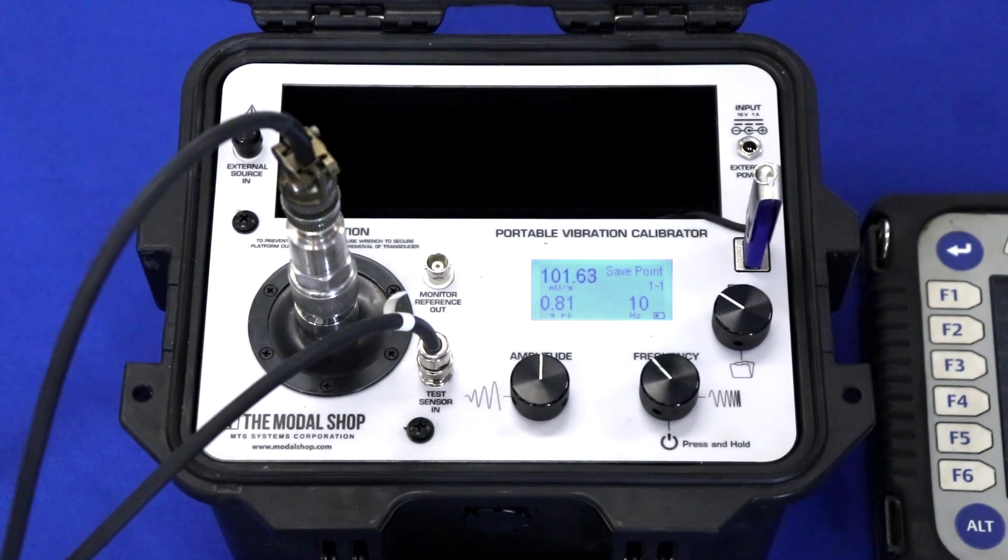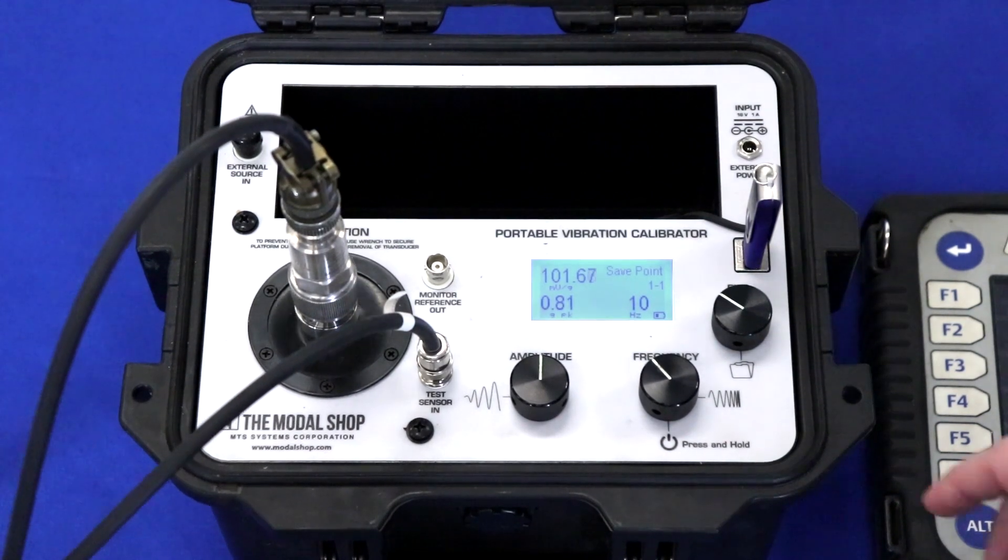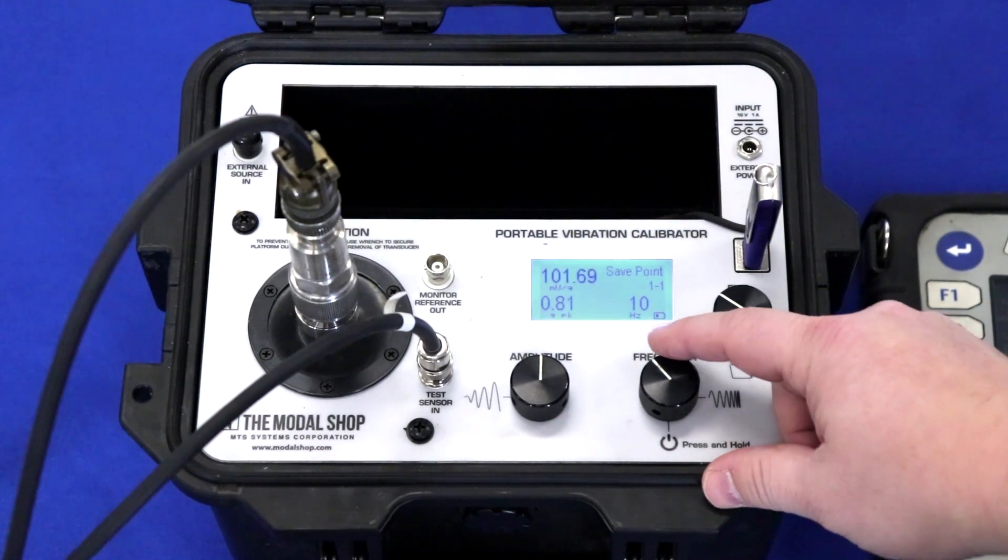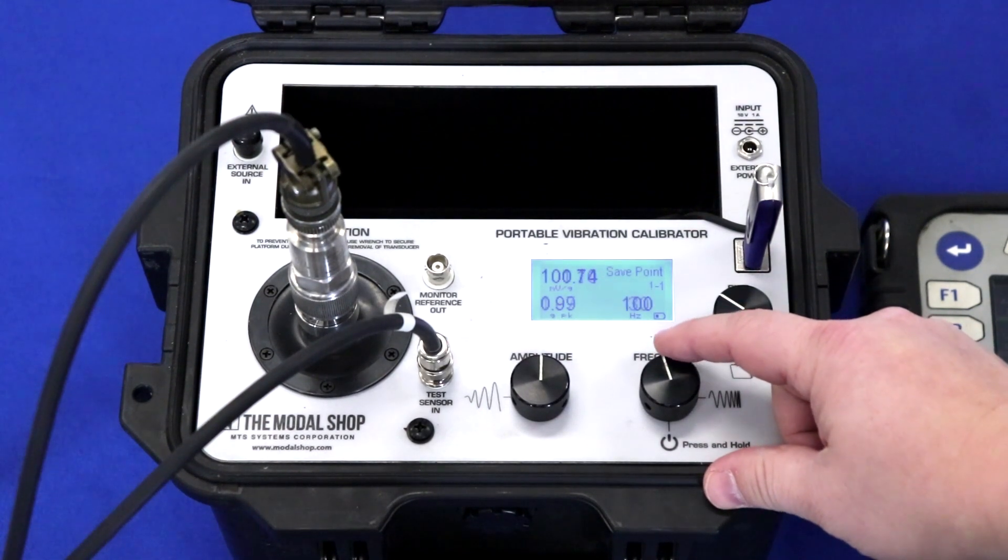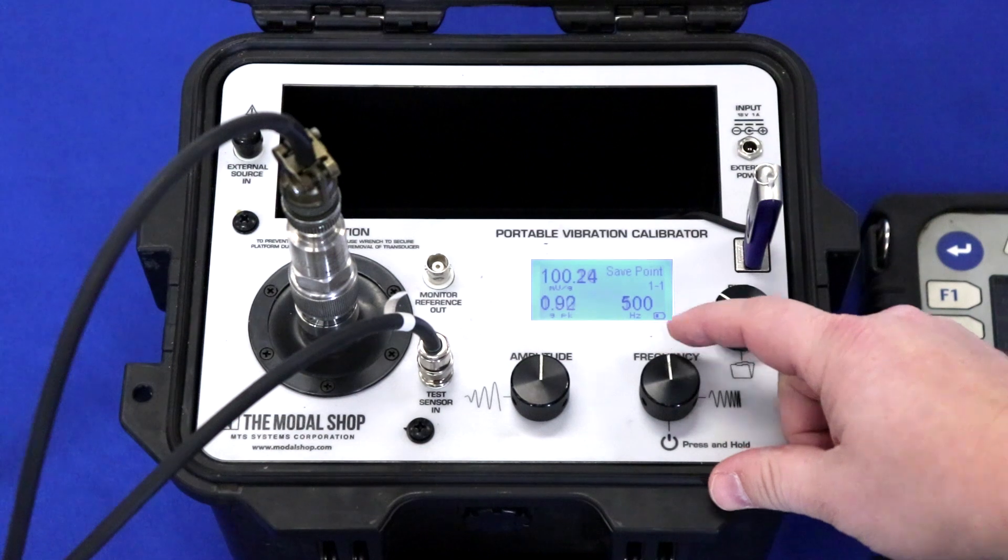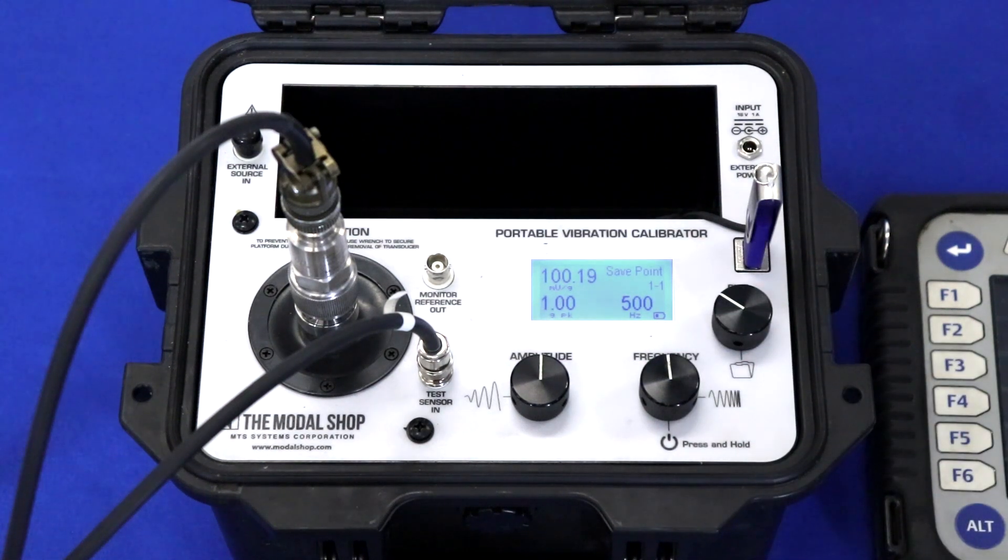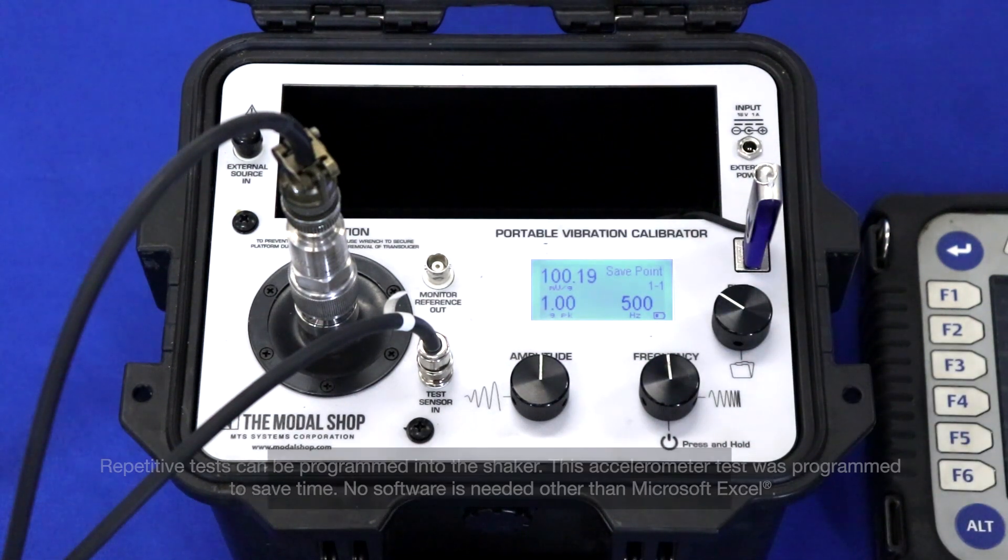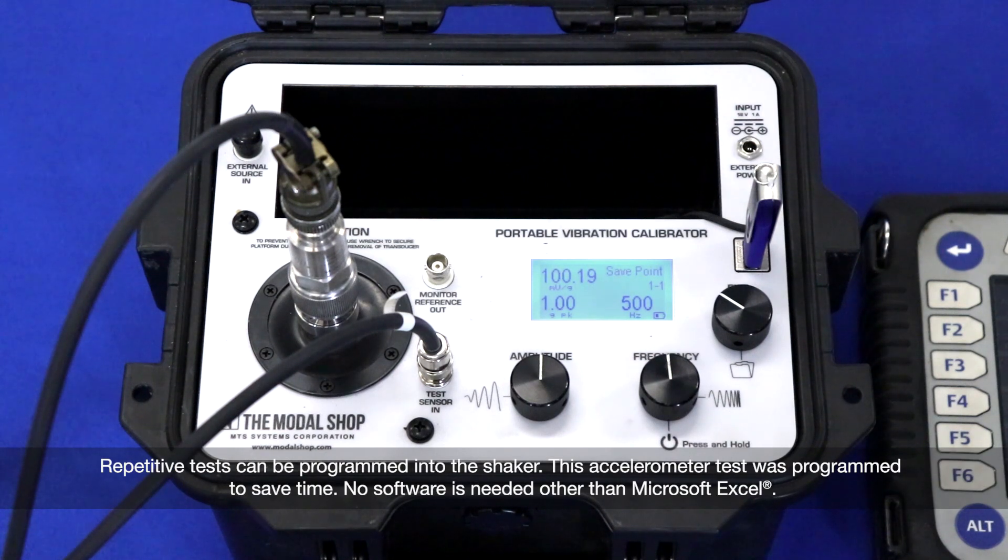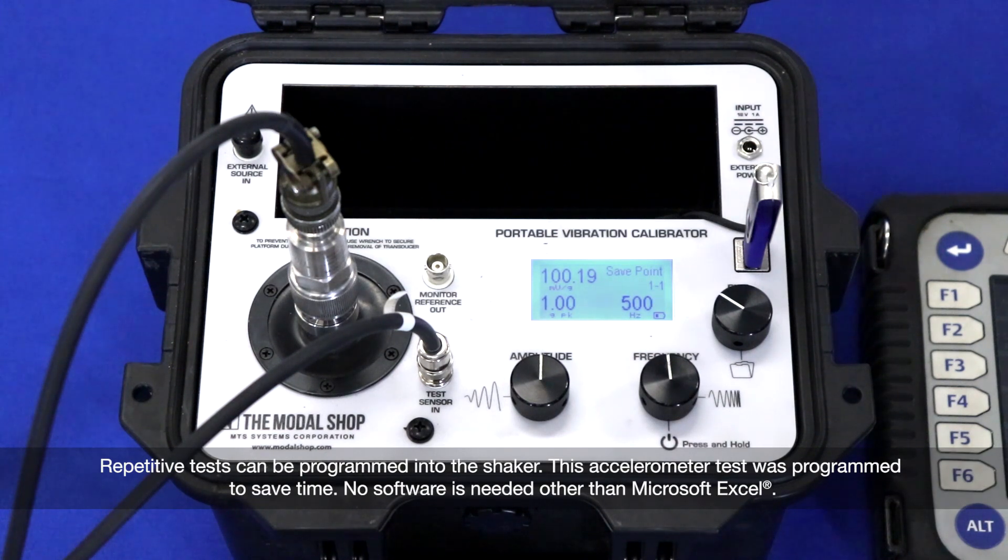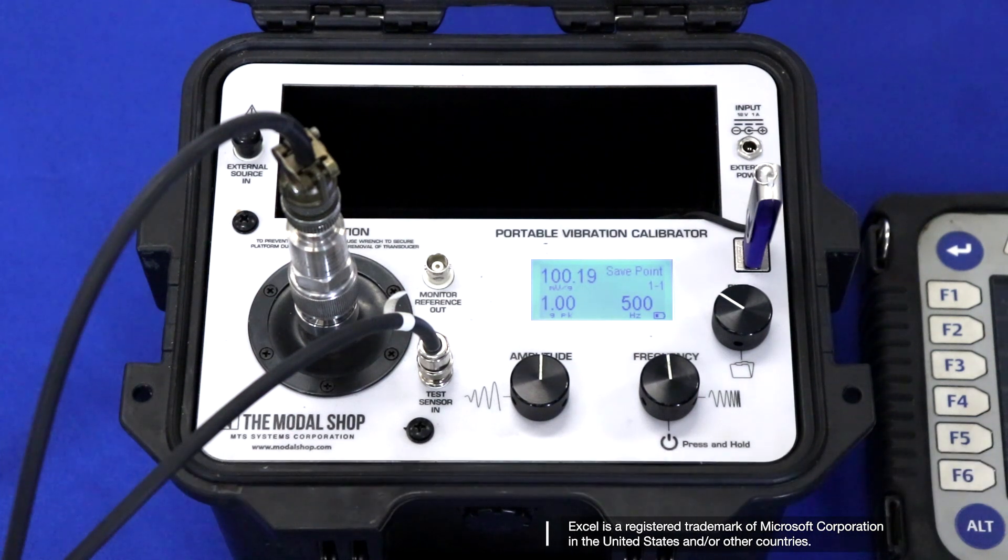And lastly, we should check the accelerometer at the high end of our velocity scale, as we'll be taking measurements in the 2130 in velocity. Let's slide up to 500 hertz and check it at 1 G peak. And you can see that the sensor is still 100 millivolts per G. Now we can move on to documenting the settings in our 2130 machinery health analyzer.